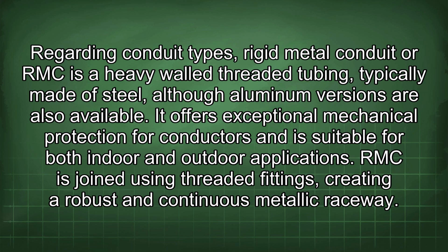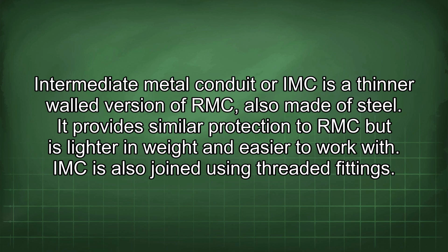RMC is joined using threaded fittings, creating a robust and continuous metallic raceway. Intermediate metal conduit, or IMC, is a thinner-walled version of RMC, also made of steel. It provides similar protection to RMC but is lighter in weight and easier to work with. IMC is also joined using threaded fittings.